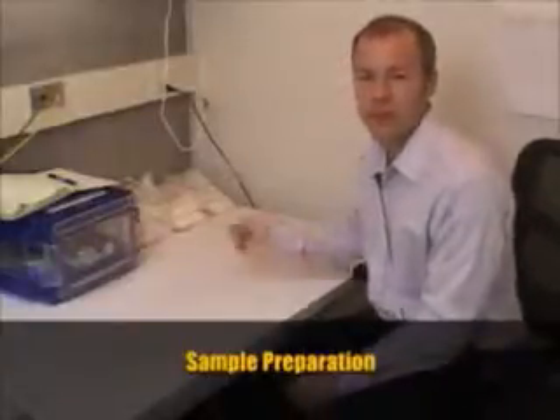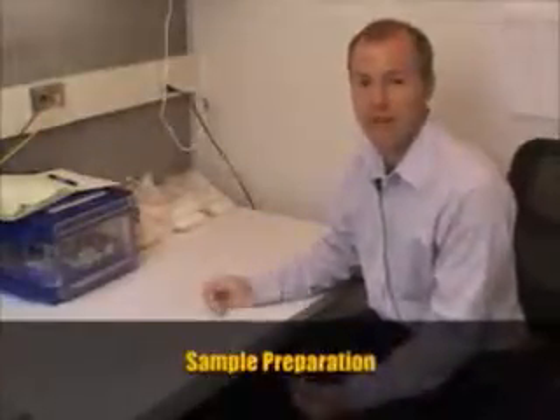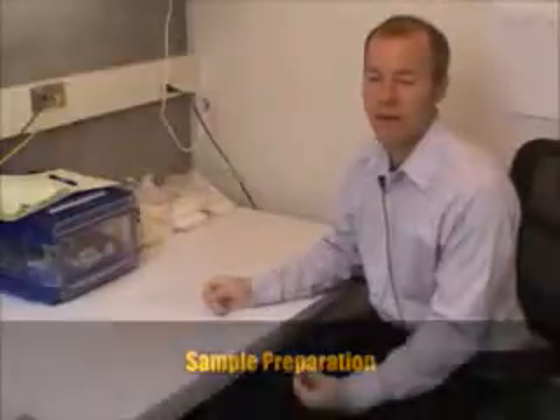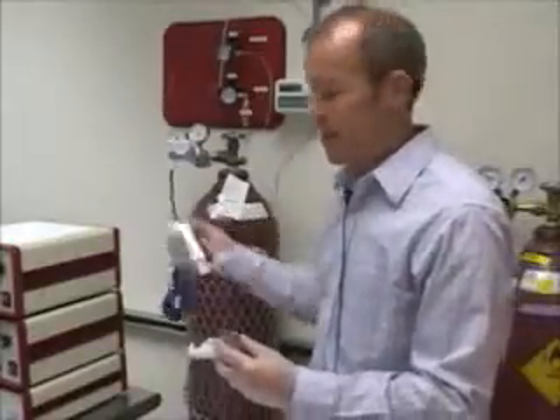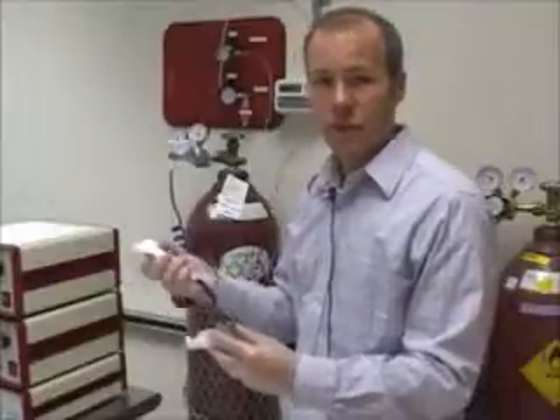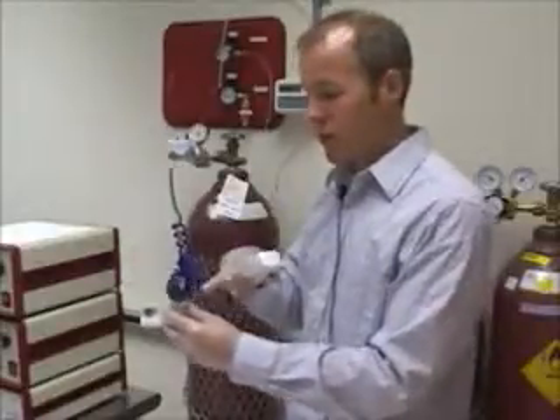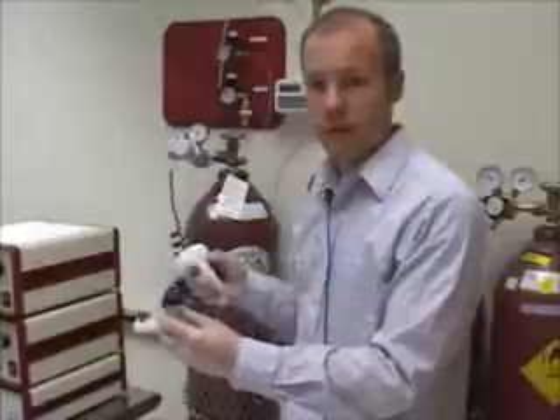Because we're putting a sample into a high vacuum environment, 10 to the minus 5 millibar, a lot of things that exist in the normal environment as liquids or solids can be vaporized. So we want to keep the sample as clean as possible, which includes keeping our finger oils off of it and also any condensation from the air. So this is ultra high purity nitrogen gas, and it's fitted with a gas gun. What I'm going to do is use a stream of nitrogen from this gas gun to just remove any loose debris from the surface of the sample before we image it.